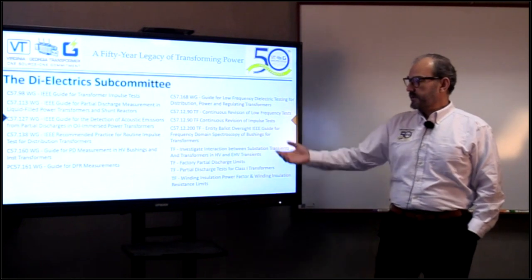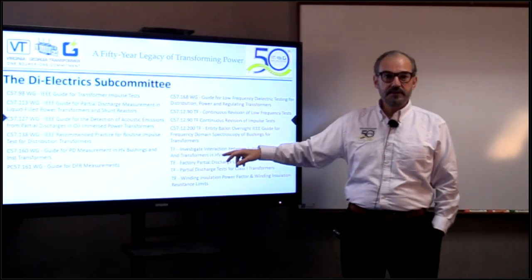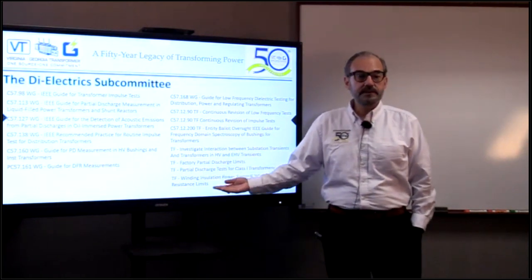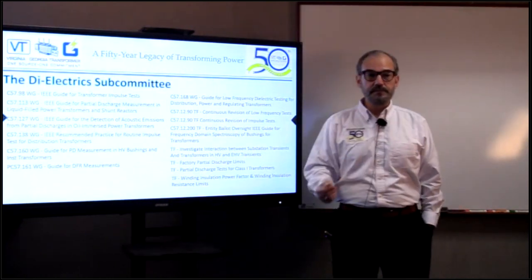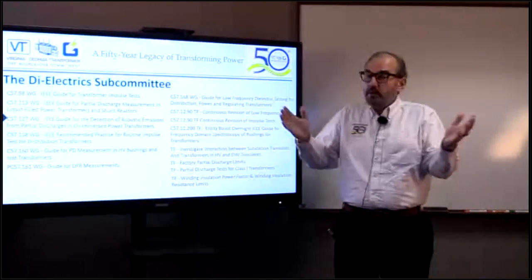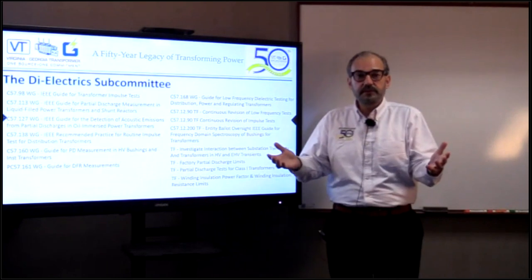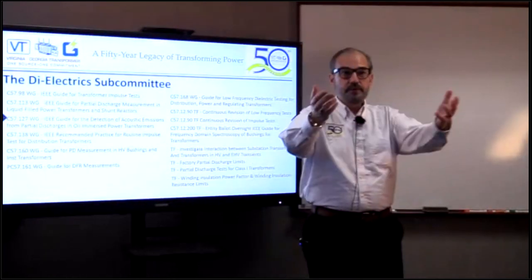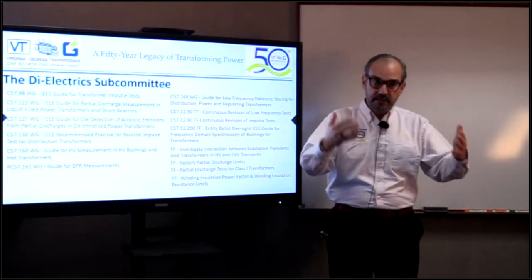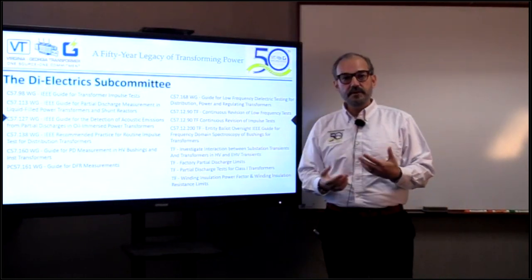There is also a task force working on the interaction between substation transients and transformers in HV and EHV applications, and another task force working on factory partial discharge limits. For example, the factory PD limit used to be 500 picocoulombs and is now 250 picocoulombs. A task force focuses on what the limits should be, votes on them, and takes the result to the working group and subcommittee for approval — this is how the IEEE Transformers Committee works.